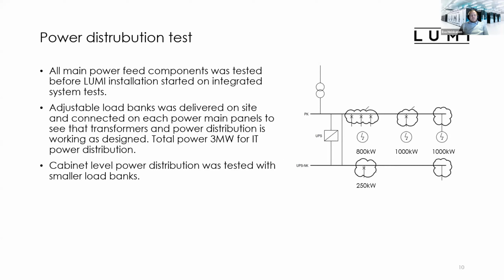About the power distribution: when the Lumi data center was built, we did it in quite a short time period, and we had to test all our components before Lumi arrived because an installation of this size hadn't been done and everything was new. So all of our main power feed components were tested before the Lumi installation started in 2021 in an integrated system test. We got adjustable load banks on site, and those were connected to each power distribution main panel to see that all of our transformers in the power distribution work as designed.